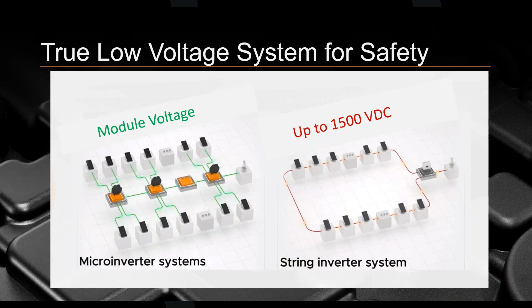Whereas for a microinverter, just by the nature of its architecture, you don't get any sort of high voltage DC at all. Because there's absolutely no presence of high voltage DC, there's basically no risk of any high voltage DC arcing since it doesn't even exist in the first place. So it is a true low voltage system for safety, since the only DC voltage you get is a single panel's DC voltage, at most 60 something volts as per NEC code.